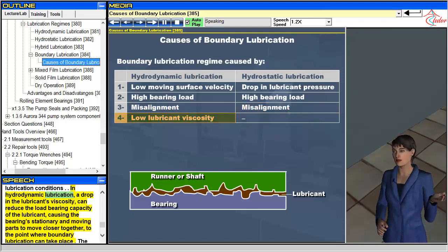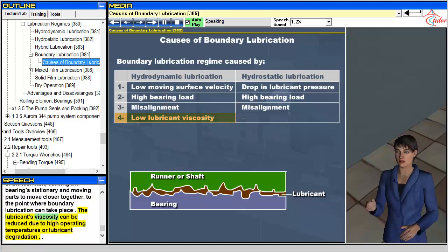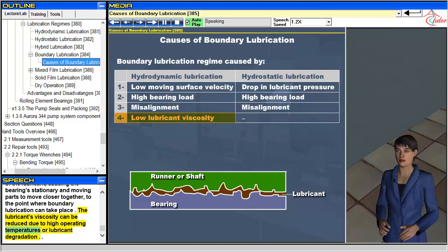In hydrodynamic lubrication, a drop in the lubricant's viscosity can reduce the load-bearing capacity of the lubricant, causing the bearing's stationary and moving parts to move closer together to the point where boundary lubrication can take place. The lubricant's viscosity can be reduced due to high operating temperatures or lubricant degradation.